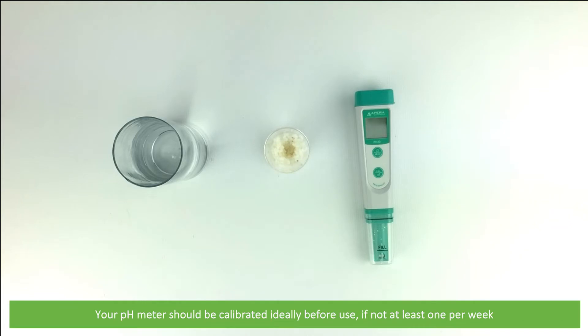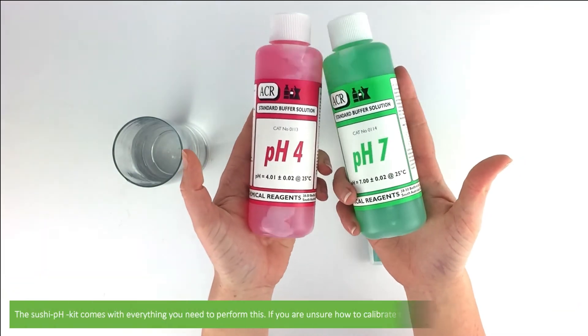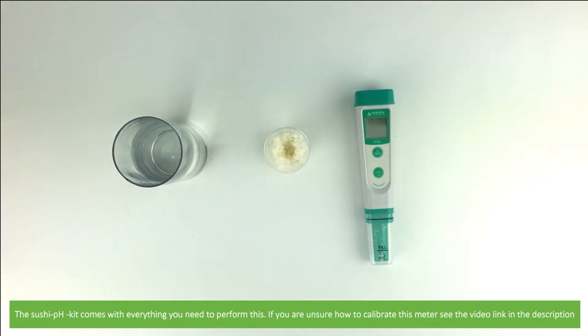Your pH meter should be calibrated ideally before use, if not at least once per week. The sushi pH kit comes with everything you need to perform this. If you're unsure of how to calibrate this meter, see the video link in the description.